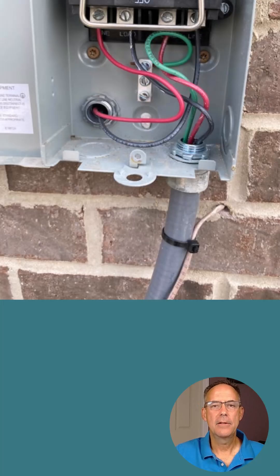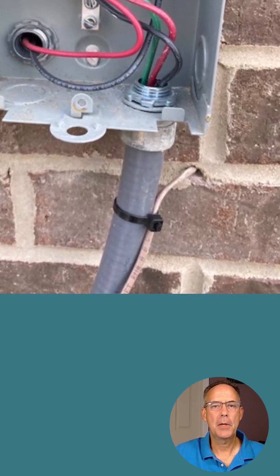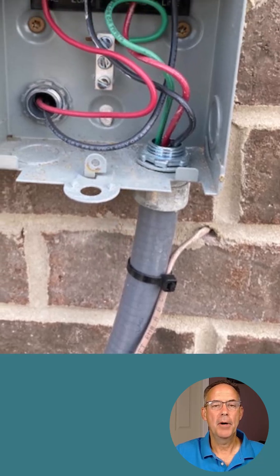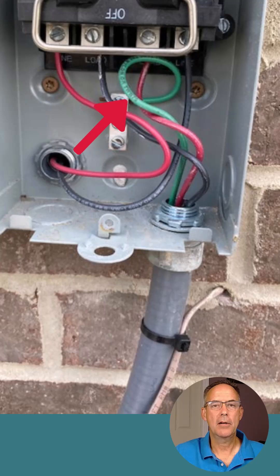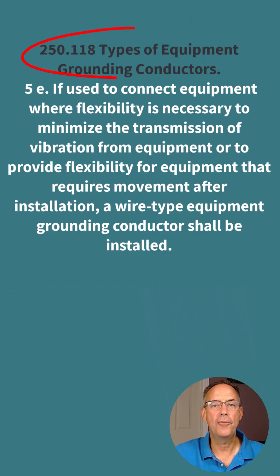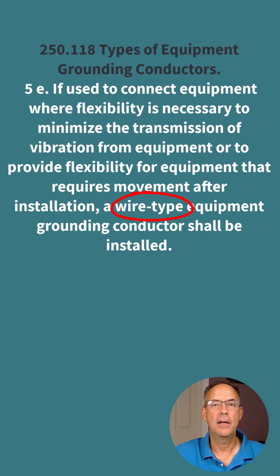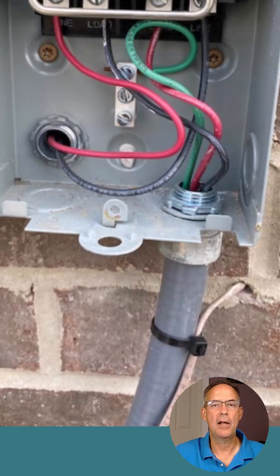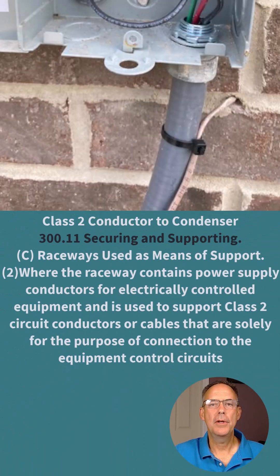From the disconnect to the unit, the code allows some type of flexible conduit such as liquid-tight flexible conduit. However, an equipment grounding conductor (EGC) always has to be provided, because according to 250.118 a wire-type EGC is required for any equipment that has vibration issues, so there is a solid fault path back from the unit to the disconnect and back to the source.